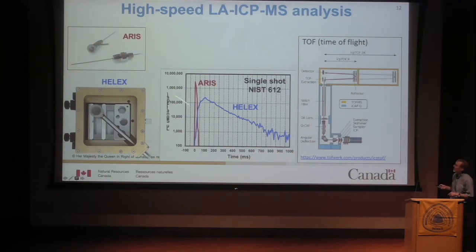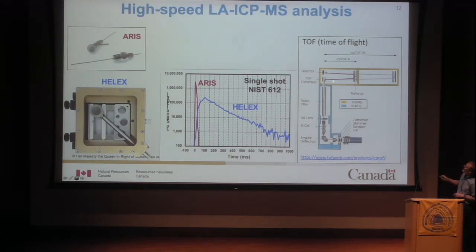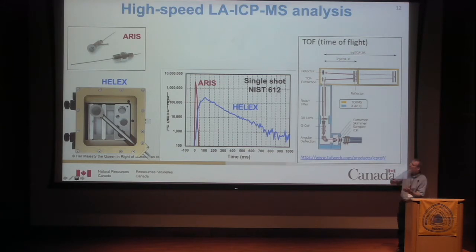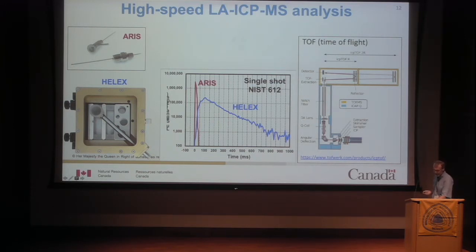This is no use for sequential instruments, but it is useful if you have a simultaneous instrument. These have started to come on the market, and the one gaining the most traction is a time-of-flight mass spectrometer, where ions are stored and then accelerated toward the detector. Because lighter ions are accelerated faster they arrive first, and heavier ions arrive later — giving packets of ions at time-resolved differences. This instrument measures the entire periodic table 30,000 times every second.